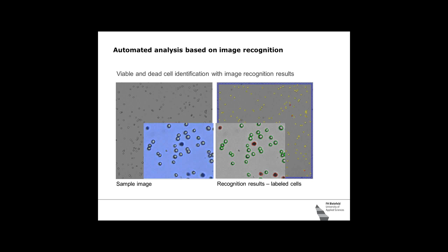And what you see here, if you ask different operators to count cells, or if you have one operator who counts cells and ask this person to count more times, like duplicates or replicates of the sample, you'll get the usual deviations between operators or between different samples being analyzed. And what is very important is that you have a device that displays sort of an average of the data that have been acquired years ago. So it is also important not to set a new standard, but to have an instrument that is able to be calibrated in a way that the data gained with this new instrument fit the data that companies presented to the FDA years ago.